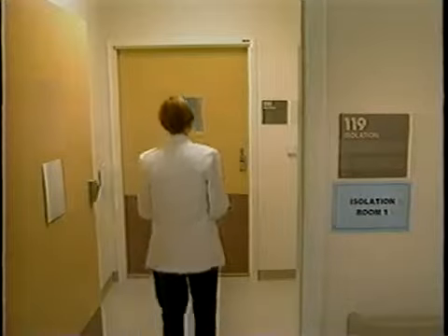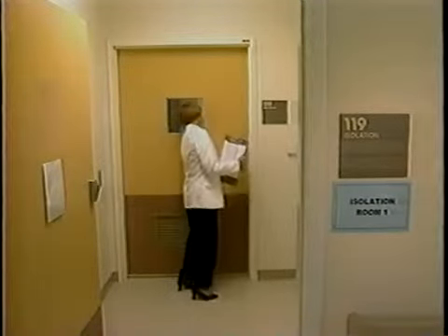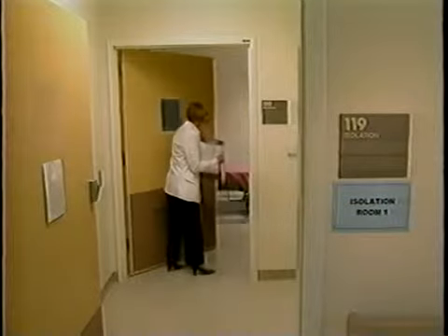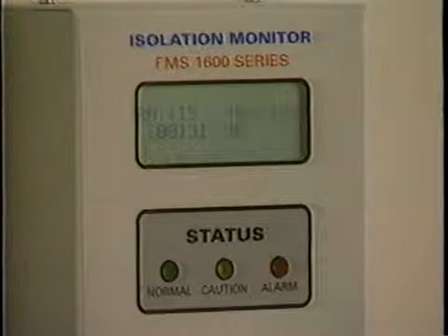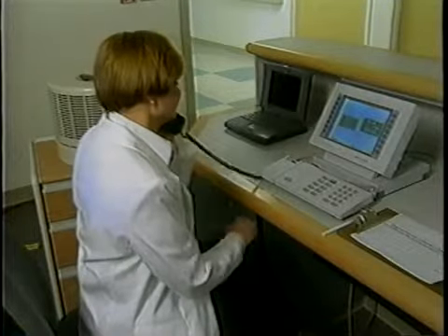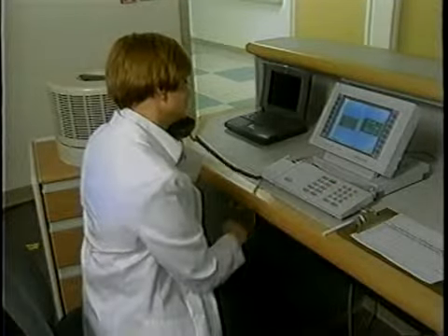You can test the monitor by holding the door open for longer than the time delay and ensuring that 1, the alarm sounds, and 2, the pressure reading goes close to 0. The monitor may be connected to a central system that will alarm at a remote location, such as the central plant or the central switchboard. Before you perform the test, make sure you coordinate with your engineering department.